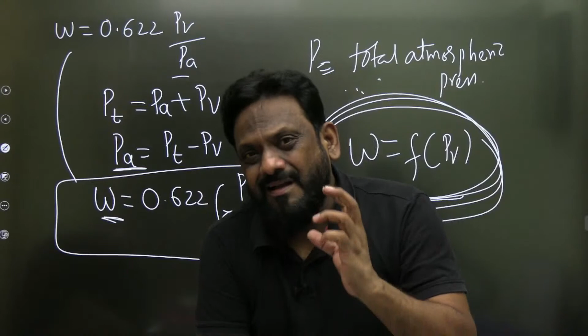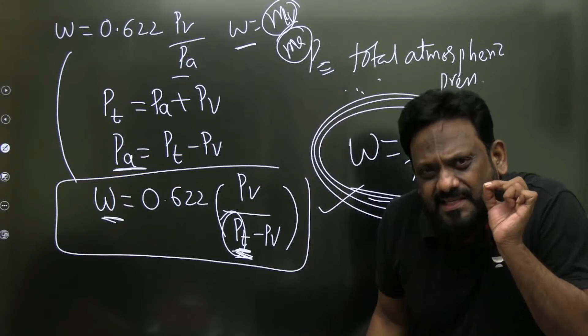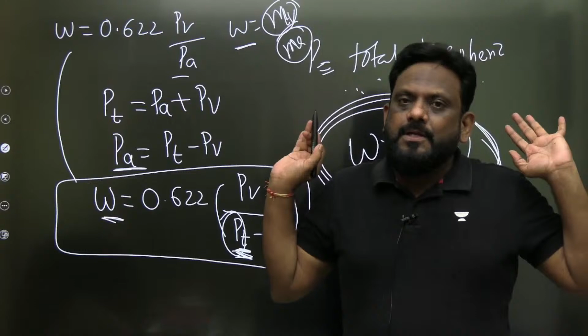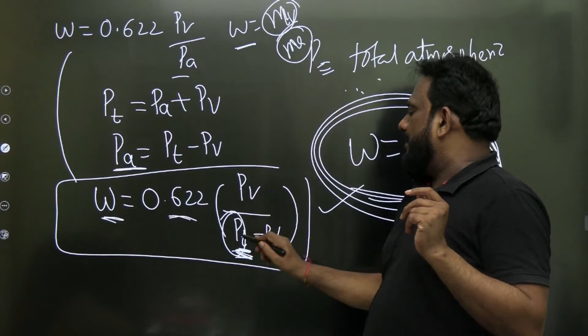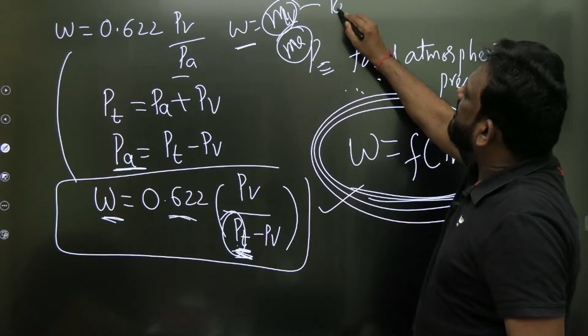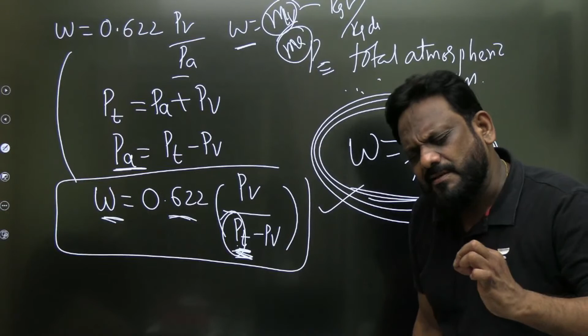What is the definition of omega? It is mv, I repeat, it is mv by ma. It is the mass of vapor to the mass of dry air. It is representing how much water vapor is present in actual air. So this is about specific humidity, and its equation is 0.622 PV by P total minus PV. Absolutely clear. And if you want to write its unit, mv is kg of vapor and ma is kg of dry air. So this specific humidity is also known as humidity ratio. Now, sometimes some people use the word absolute humidity.